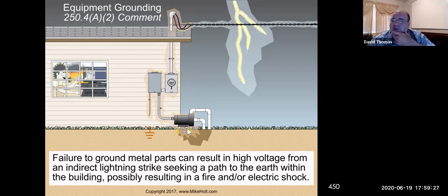So this is, if we fail to ground things, metal parts can result in high voltage from an indirect lightning, and they may seek a path to earth within the building, possibly resulting in a fire or electric shock. So what we're trying to do is ground everything before it gets in, to get it to earth as quickly as possible. So at the panel, this wire is broken here. The wire was meant to be attached to my ground rod or whatever this is, possibly a ground rod. And so if lightning were to hit those wires, we want to redirect it down to earth before it comes into the building. And that's kind of why we ground at the main panel.